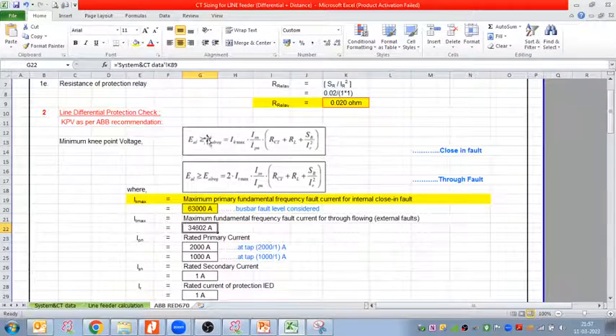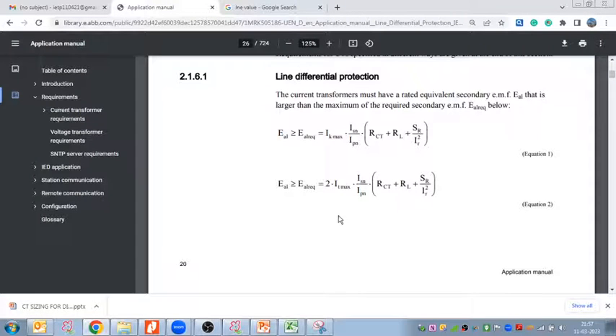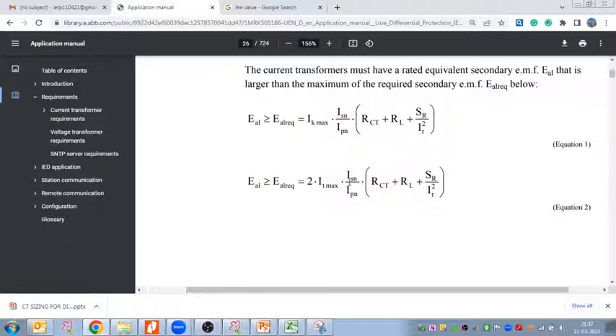Once my through fault current is calculated, I will go and put the same fault current here in the second equation. All the inputs of the first equation are clear, but for the second equation, let me check from here. 2 IT max ISN, this much.